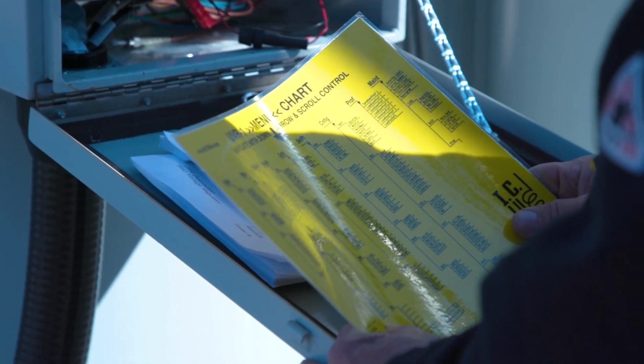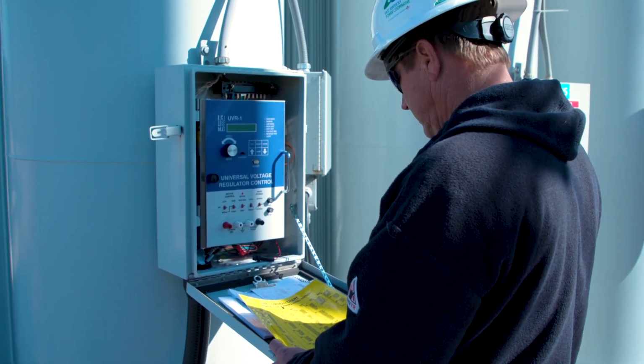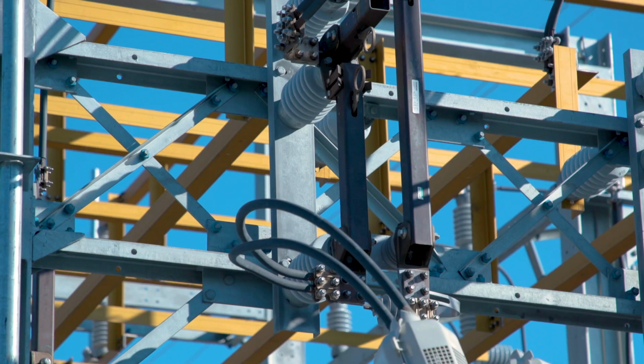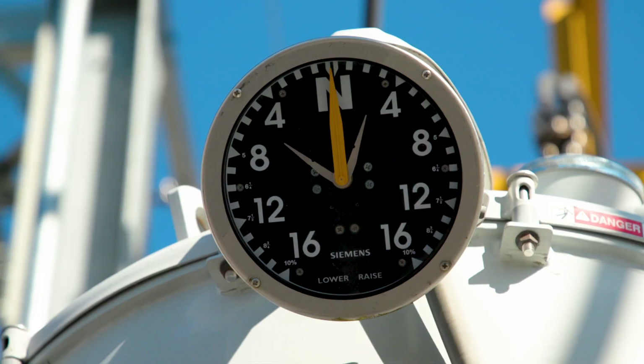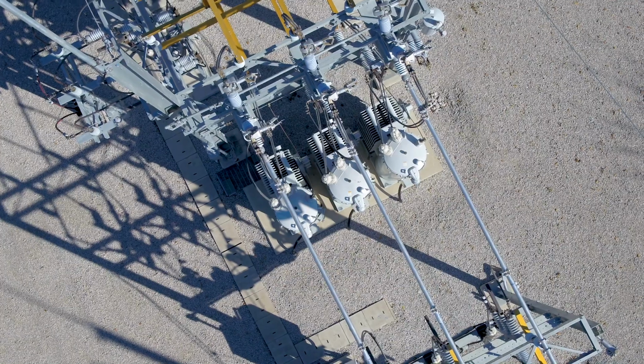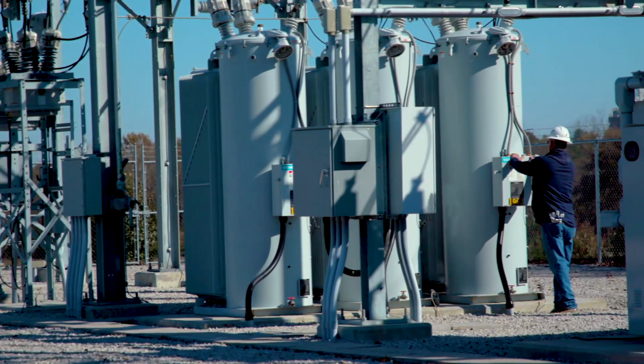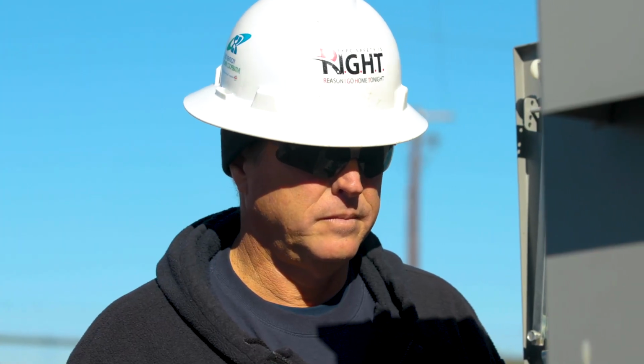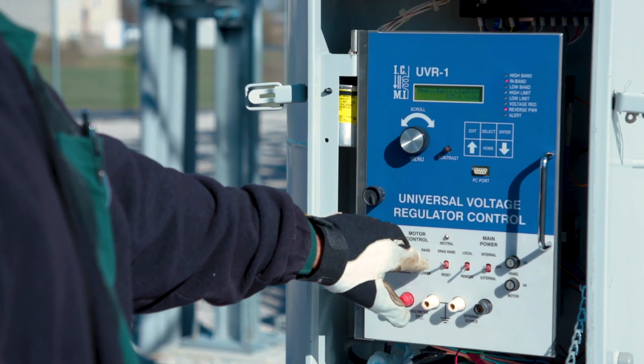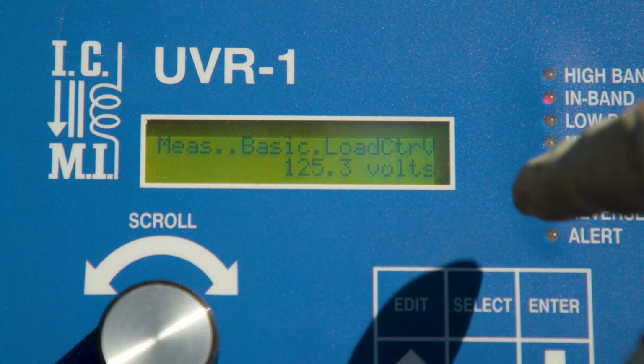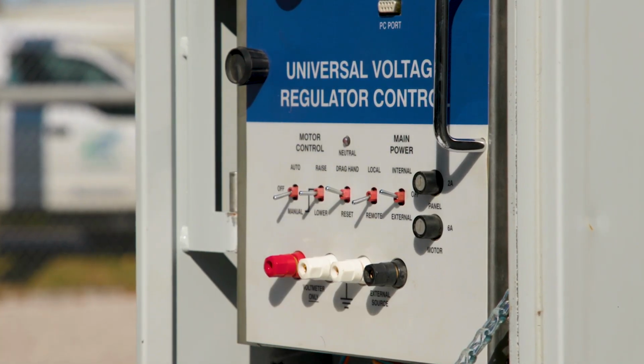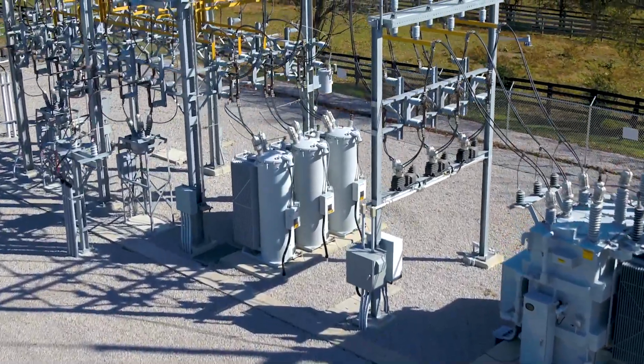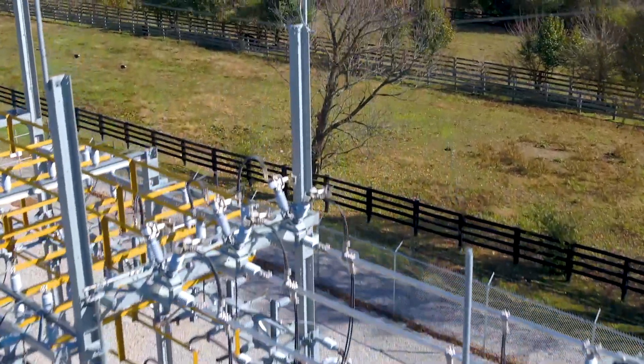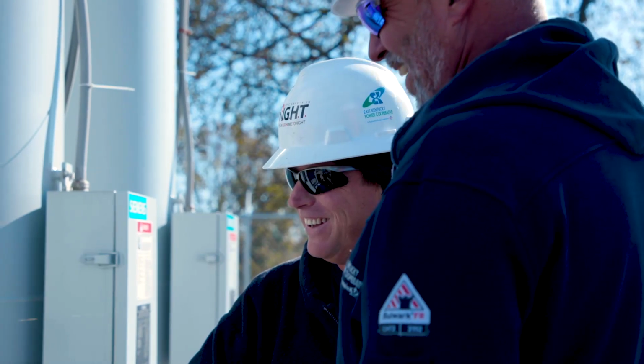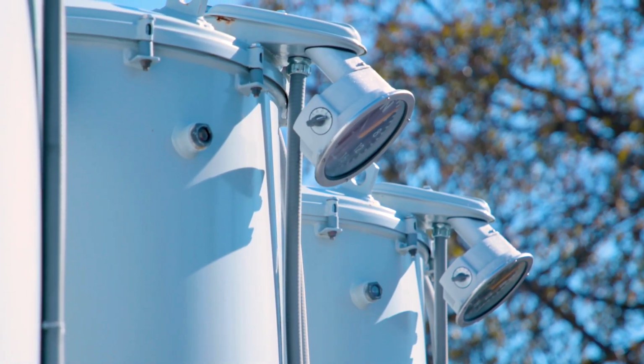For those who need more detailed information about the regulator controls, there is a safety sheet inside the cabinet that explains how the controls operate. Keep in mind that before bypassing a regulator, always verify it is in the neutral position. And it is also important to remember that the regulator can be controlled manually. The key functions on the regulator control include tap position control, auto, manual, the neutral indication, measured regulated voltage, and remote local. This last function senses the voltage on the system to determine if the regulator should step up or down. Through an internal potential transformer connection, the regulator control measures regulated voltage and adjusts accordingly.